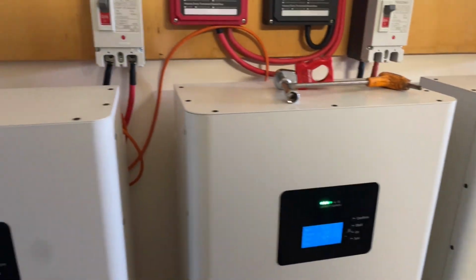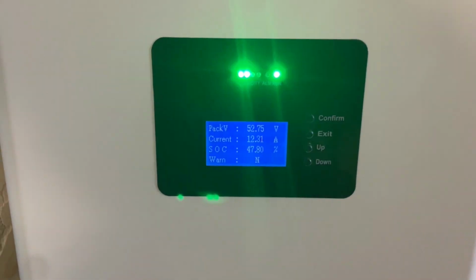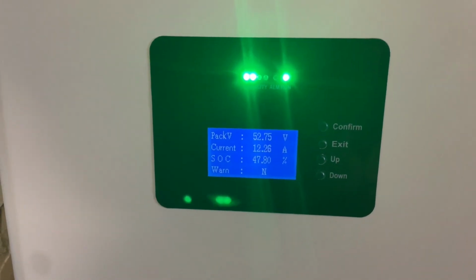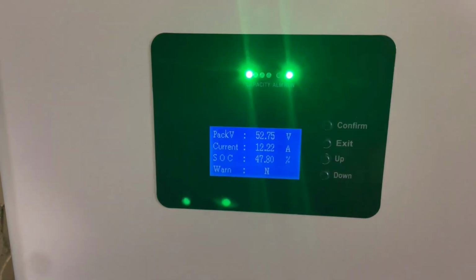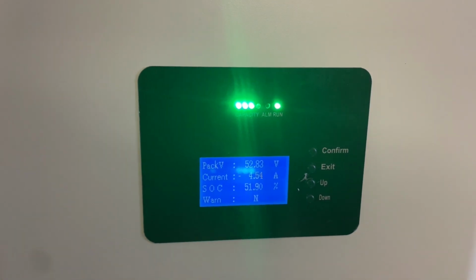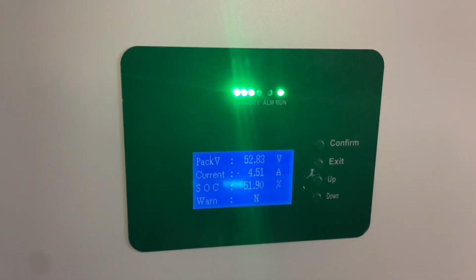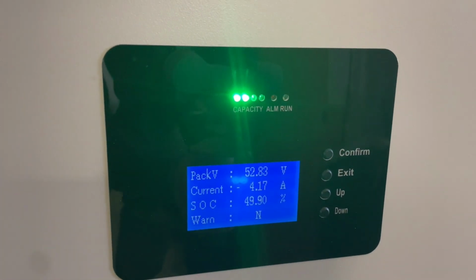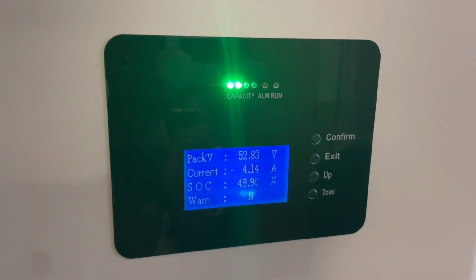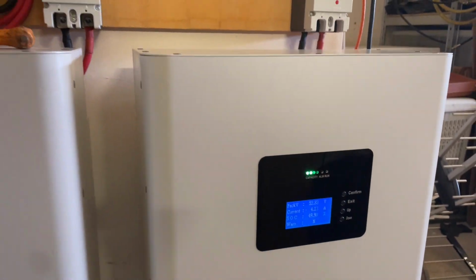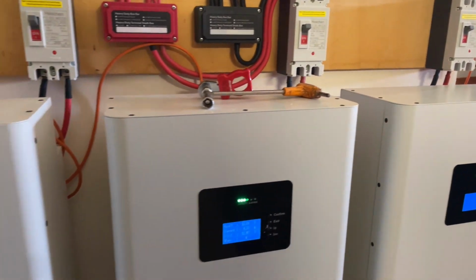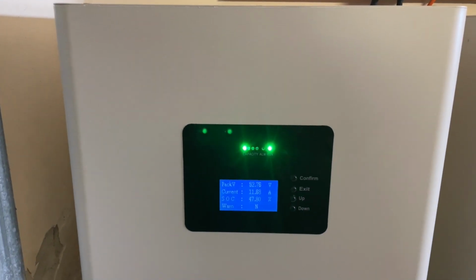It looks like the charge controller and the BMSs are talking to each other. This battery at 47.8 has got 12.2 amps going into it. This one at 51.9 is drawing 4.5 amps, and this one at 49.9 is drawing 4.1. So the BMS of all three batteries is talking to each other, and it's looking to bring the battery that's at a lower state of charge up.